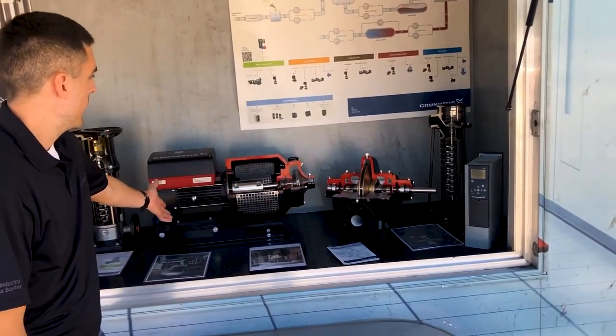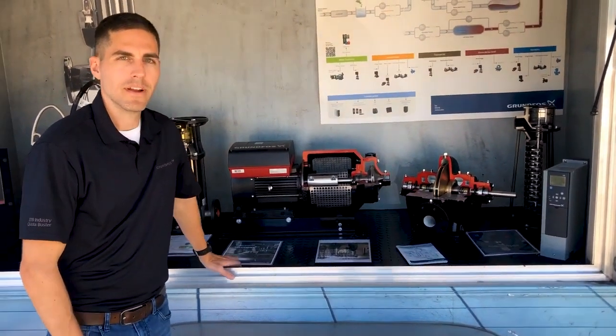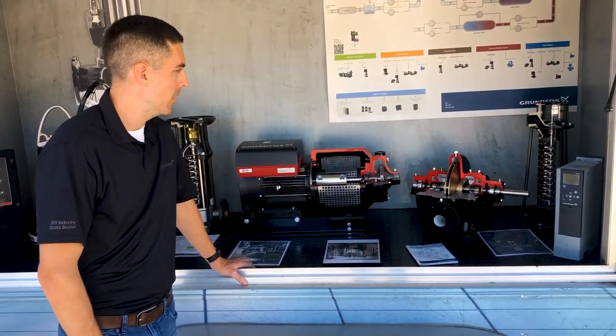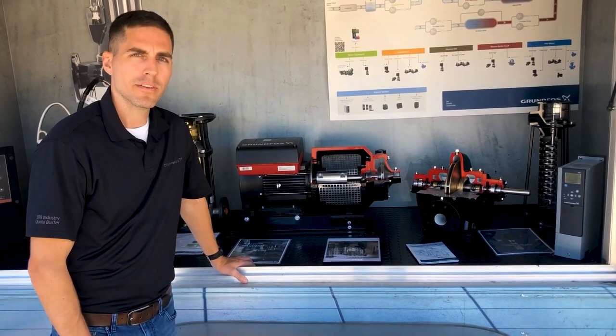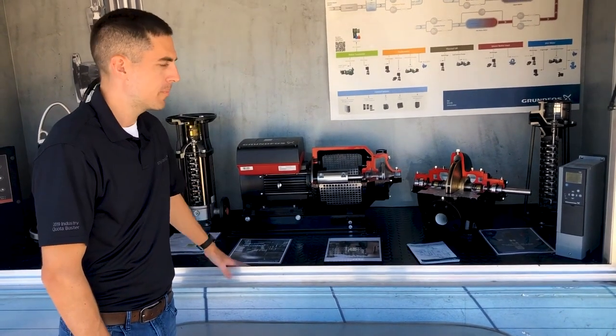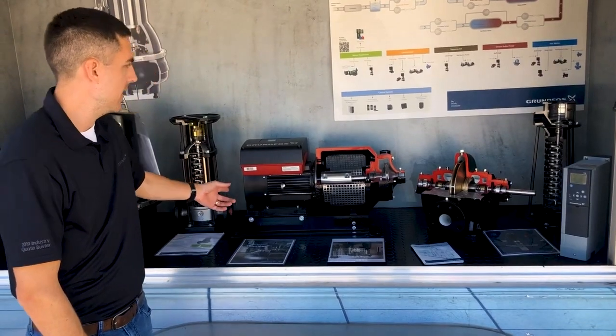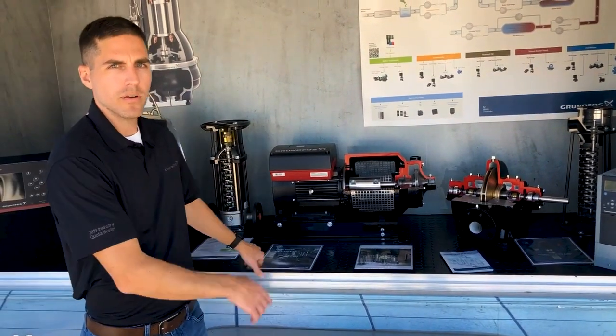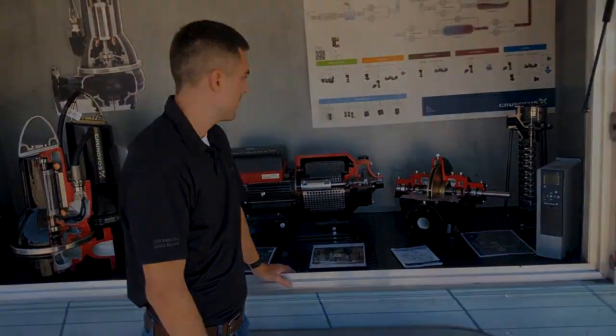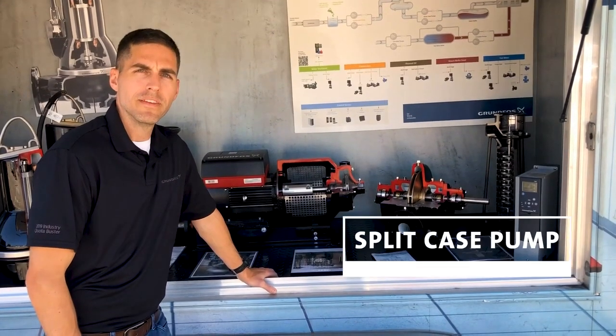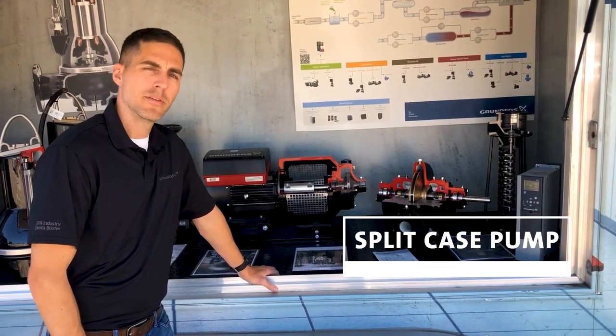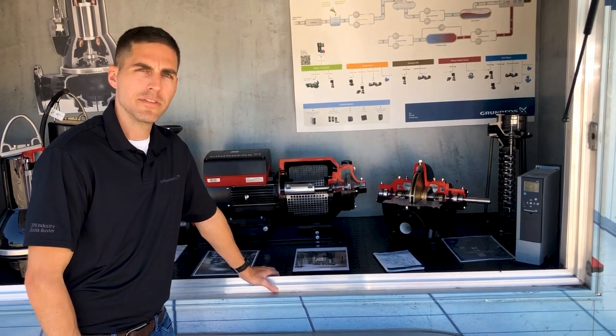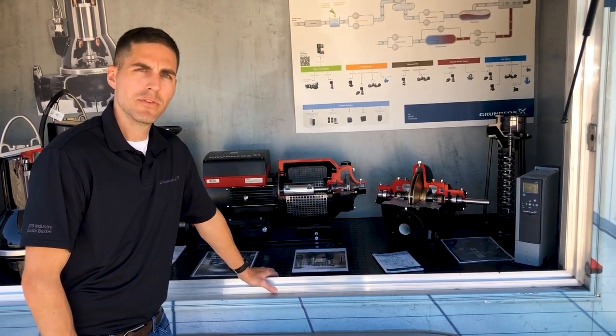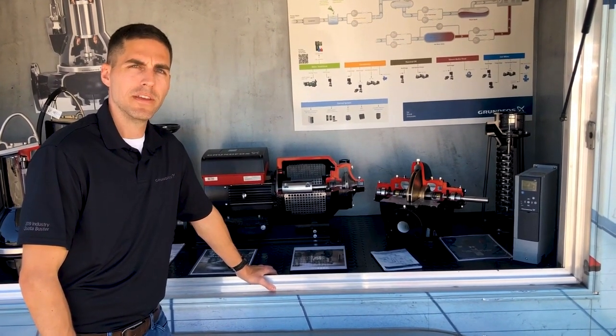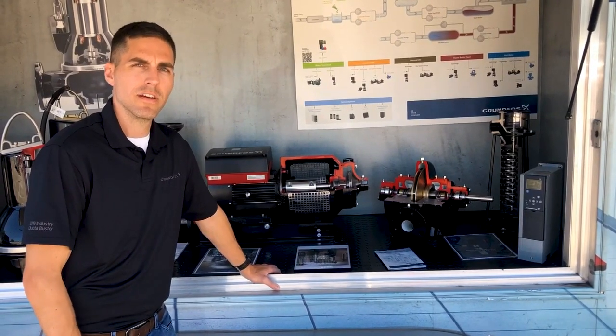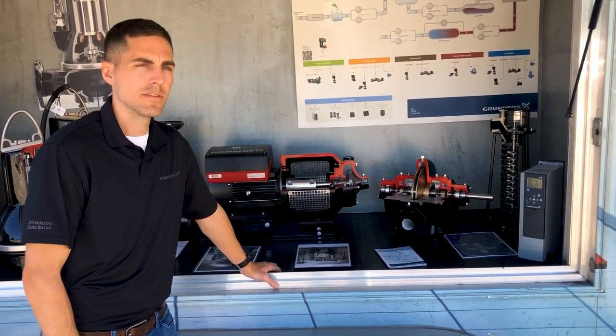Right next to it, in the center here, are the two pumps that I'd like to focus on. These are both Paco pumps. Out of all the Paco products we build here, these are the two most popular models. We have the split case and the in-line pump. So I'll start with our Paco KP, or the split case pump. The Paco split case pump is a single stage pump. The impeller is made out of either bronze or stainless steel, and it can be trimmed to a custom diameter to meet the customer's specific flow and head needs.